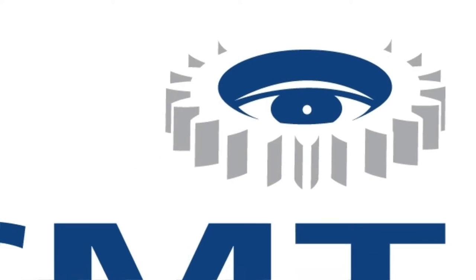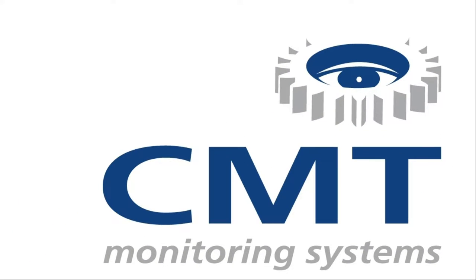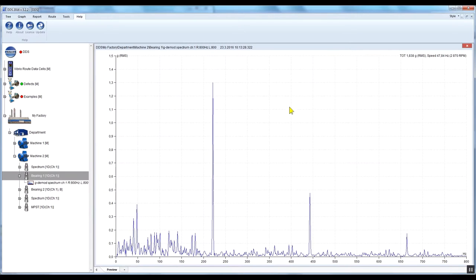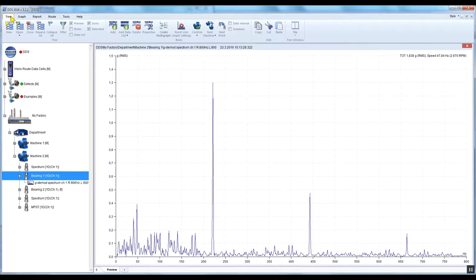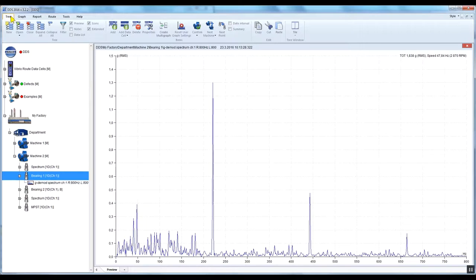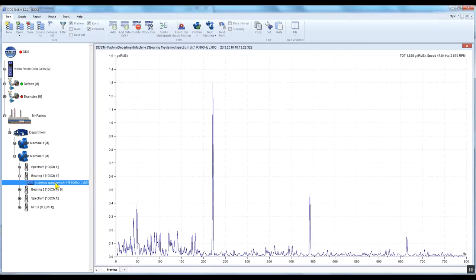This is the DDS tutorial video. In this video I would like to show you how to display bearing fault frequencies. DDS software contains a bearing database with about 30,000 bearings with information about their bearing fault frequencies. This tool can be very useful for bearing fault analysis. We will be working with a demodulated acceleration spectrum in G units, also called an enveloped spectrum, which is commonly used for bearing fault analysis.